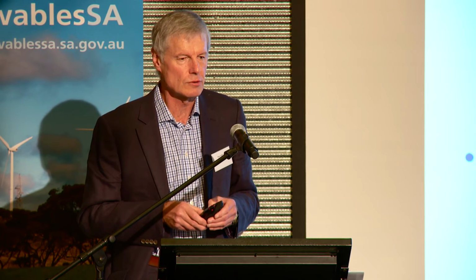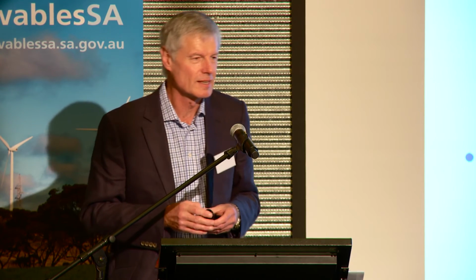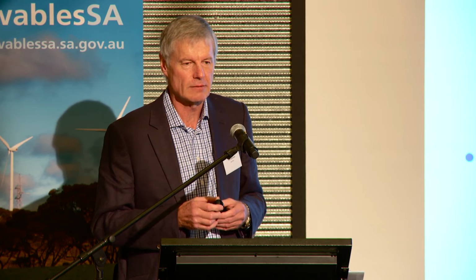Now at the smaller scale, you tend not to get the ability to have very high steam conditions, and so what you can do is you can burn the process rather more cheaply at a lower temperature, and instead of using steam as a working fluid to produce electricity, you can use an organic fluid, and that's normally called an ORC, or an organic Rankine cycle, which means you can use lower quality heat and you can still convert that into electricity. This has become popular also for geothermal power stations. If you don't get high quality geothermal steam or geothermal hot water, you can use an organic cycle. And similarly, you can use organic Rankine cycles to convert low-grade heat out of other engines.